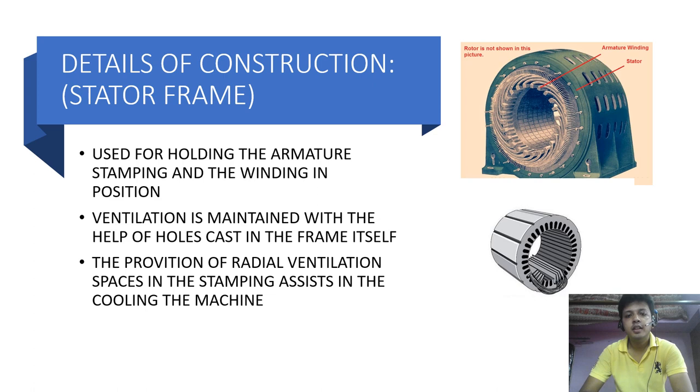In DC machine the outer frame or the yoke serve to carry the magnetic flux, but in alternator it is not meant for that purpose. Here it is used for holding the armature stamping and winding in position. Low speed, large diameter alternator have frames which, because of ease of manufacture, are cast in section. Ventilation is maintained with the help of hole cast in the frame itself. The provision of radial ventilating space in the stamping assist in cooling the machine. But these days, instead of using casting, frames are generally fabricated with mild steel plate welded together in such a way as to form a frame having a box type section.